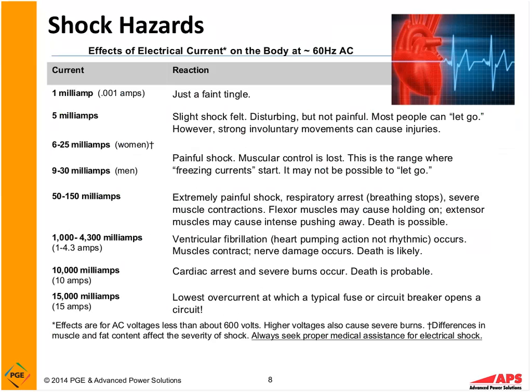So when we look at shock hazards, it doesn't take a lot of current to create a significant shock hazard. When we look at just a faint tingle, 1 milliamp, that's 0.001 amps. Very little current flow here at 1 milliamp, just a faint tingle. At 5 milliamps, just below it, slight shock felt, disturbing but not painful. Most people can let go. However, strong involuntary movements can cause injuries.